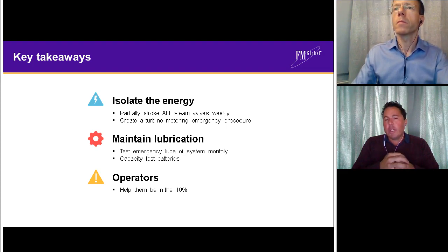So from an operational perspective, the impact would be significant if you're losing vacuum on a regular basis and suddenly. But generally speaking, I believe, and I'm an electrical engineer, so I'm not a mechanical specialist or a metallurgical specialist, but I suspect what you'll see there is a reduction in the life of the turbine rather than a discrete event at that point that takes the turbine out of service.